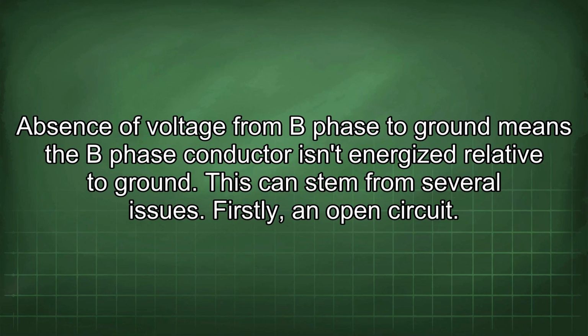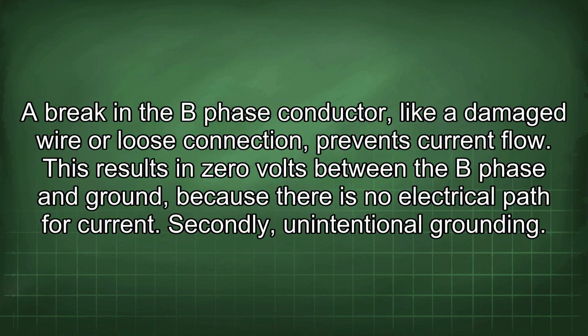Absence of voltage from B phase to ground means the B phase conductor isn't energized relative to ground. This can stem from several issues. Firstly, an open circuit. A break in the B phase conductor, like a damaged wire or loose connection, prevents current flow. This results in 0 volts between the B phase and ground, because there is no electrical path for current.